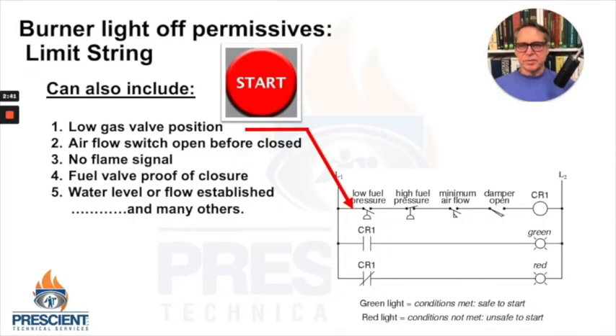So let's get back to what happens when we hit the start button. There's a thing called a limit string. This is a sequence of contacts that are in series. These are devices or conditions which have to be in a certain state before a next sequence of light-off events can occur. So at a minimum, they're typically things like fuel gas high and low, minimum airflow, maybe there's a damper that needs to be open, but it could be proving that low gas valve position is indeed made.